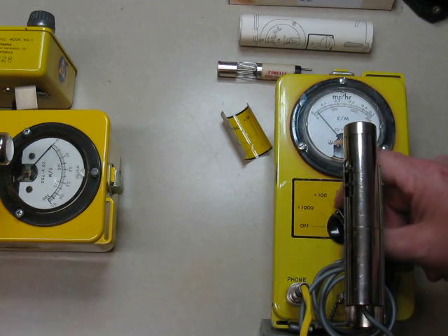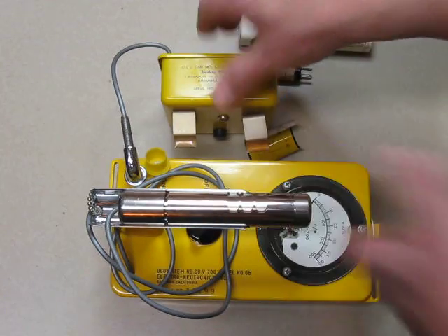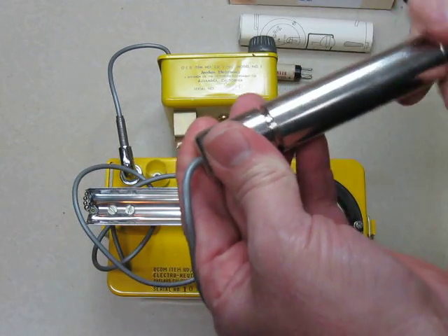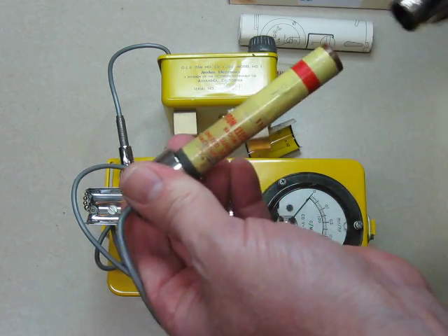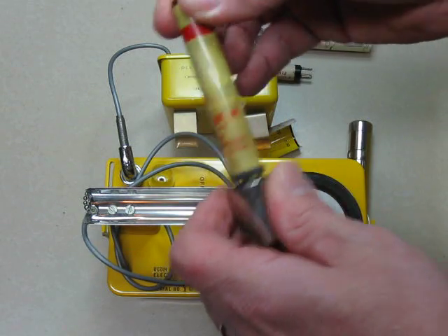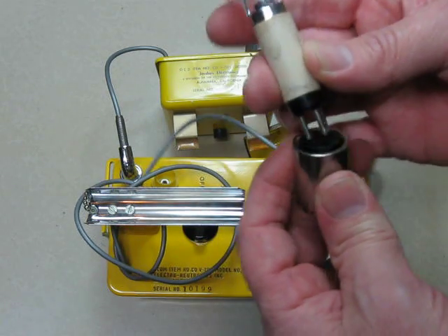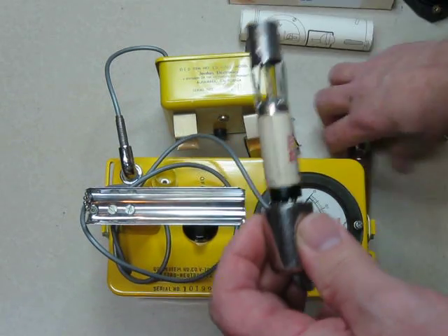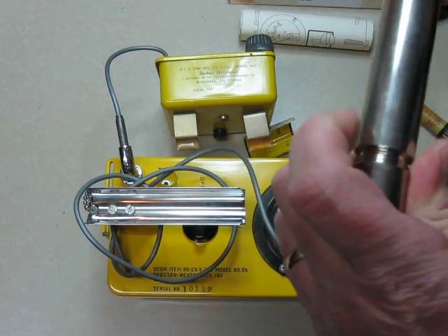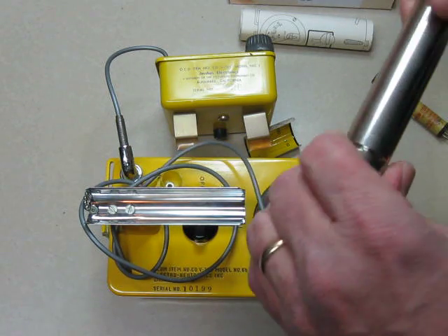We'll go ahead and turn this one off and bring our other one over. The one with the standard 700 tube in it - we'll turn it off and take the tube out of it. This has got a 6993 tube in it - it's an Anton tube, because this ENI did not have a tube with it when I got it. We'll take the Anton tube, plug it in, and put the probe housing back over it. I'm not going to tighten it all the way down.